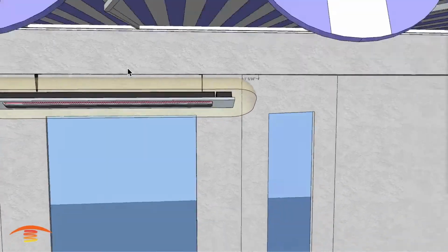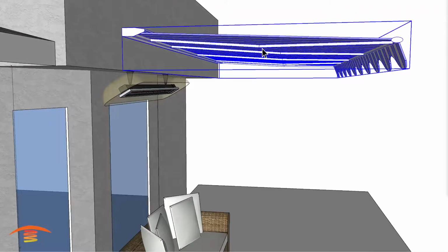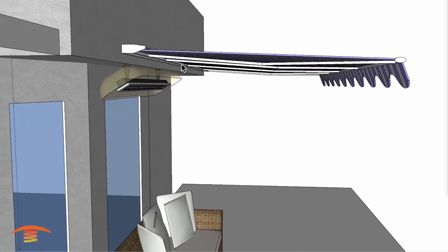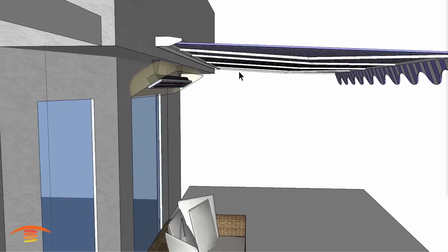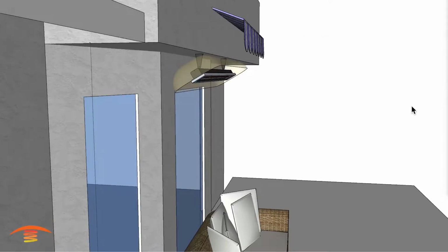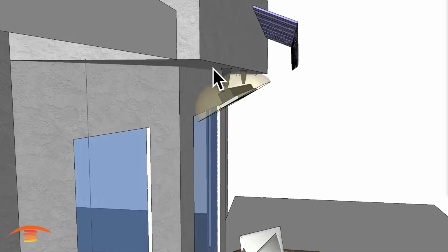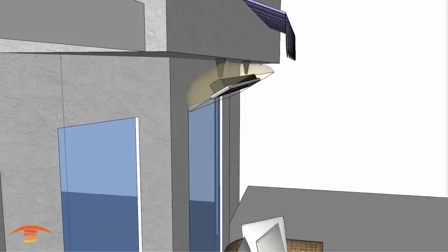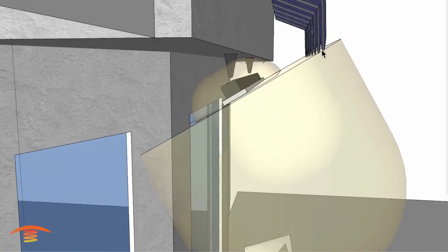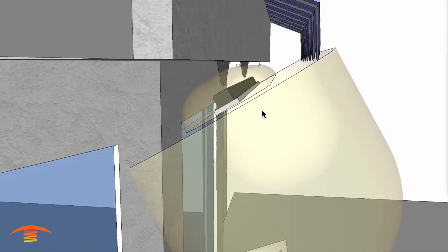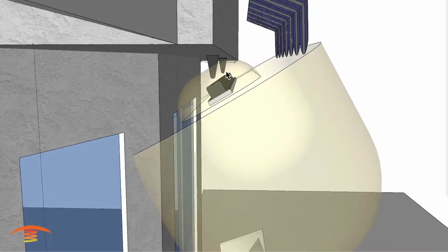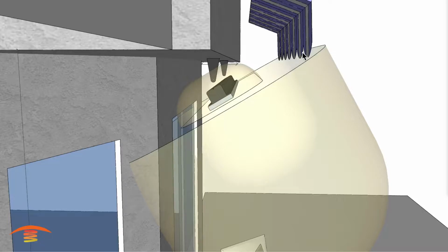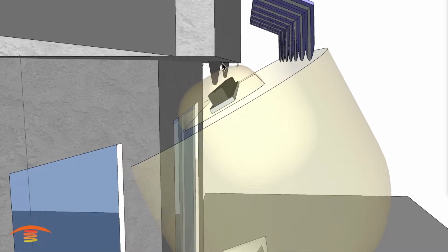So if that awning structure is down, let's say, a few inches here, if it's extended, it's okay, but this is a retractable awning. So the retractable awning, I'm going to go ahead and show what it might look like. It needs to be at the same elevation as the overhang here. And that overhang, again, I'm going to look at the bottom clearance. This is why, because you need to make sure that this isn't draping down in front of the heater itself. So the only way I can say yes, that it would be functional, is if when retracted, the elevation of the bottom edge of the fringe, I guess you'll call it, is at the same elevation as the bottom edge of this overhang.